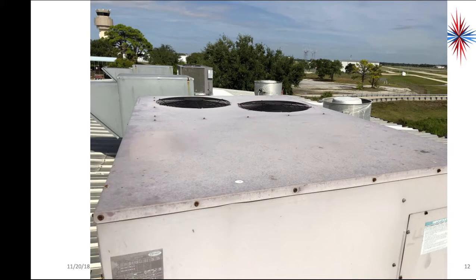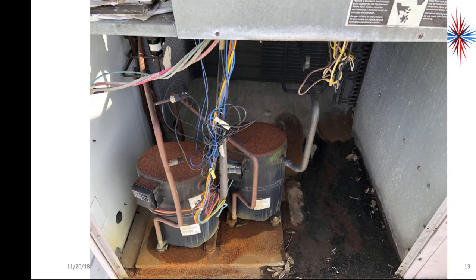We look at the data plate because there's some things we're after. I want the run amps, I want the LRA for the compressors, I want the condenser fan motor amps, and I want the blower motor amps. I did cut off the model and serial number here just for some privacy for the people that own this unit. Okay, so again, further look around just gives us a better idea of what's going on.